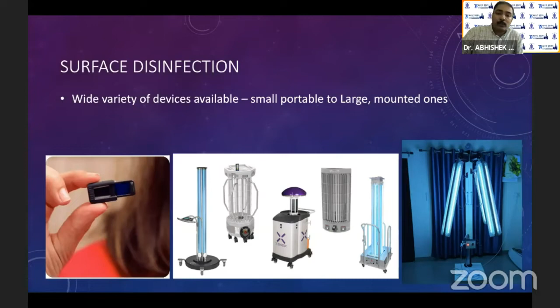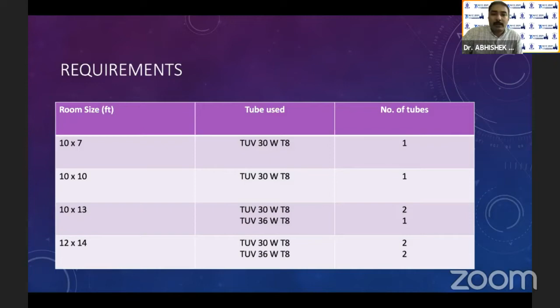For a room, if you want to make sure that your consultation room or your waiting room is sterilized, this is a rough guideline that is found somewhere in the literature. If you have a 10 by 7 room, like an optometric cubicle, a 1 x 30 watt tube light is enough. But if you have something like a 10 by 13 or a 12 by 14 room, then either 2 x 30 watt or 1 x 36 watt for the smaller room and 2 x 36 watt for a bigger room, either on opposite walls or in two opposite corners. You need this light to be able to achieve a kill properly. So this is an example of how I have been using it.